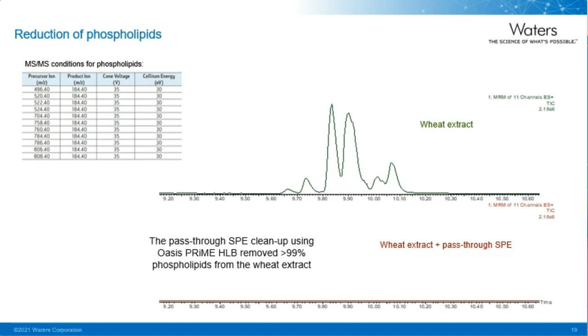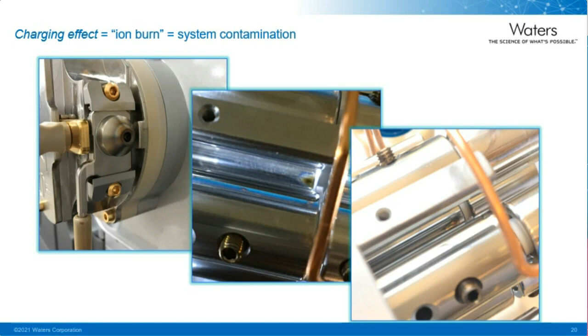Charging occurs when the amount of charge being deposited onto a surface is greater than the rate at which the charge is dissipated. These are images of a TQ-XS after over 1 year of good service. And we can see how different metal components become contaminated by the so-called ion burns. The time scale of this effect is directly related to the ion current being injected into the MS. So it is highly advisable on highly sensitive instruments to minimize the number of unwanted ions being introduced into the MS. It is important to note that this is true for all mass spectrometers for all vendors. They all become contaminated over time, and at some point they need cleaning.